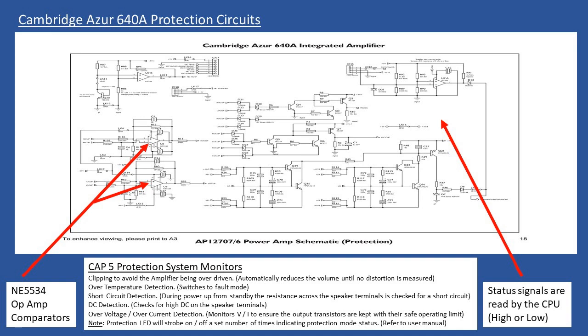So what we do here is, via the comparators and the transistor switching circuits, depending on the fault condition, we're making it high or low. Normally, low means there is no fault with any of the circuits, but if any of them trigger, then that pin will go high, and that would be read directly by the microprocessor. The firmware code would then run and carry out the particular operation that was assigned. In some cases, it just de-energizes the speaker protection relay and then will flash.